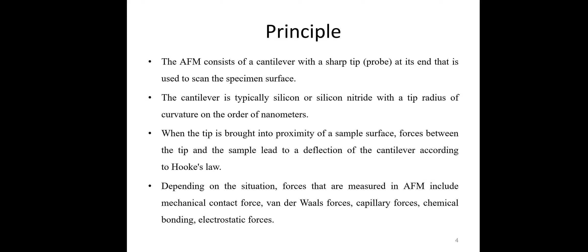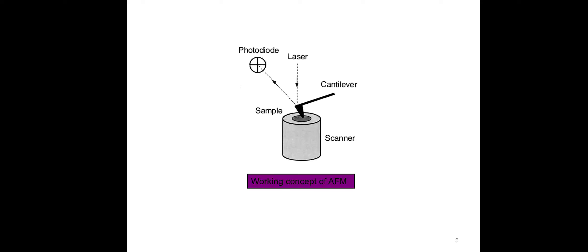Depending on the situation, the forces measured in AFM include mechanical contact force, Van der Waals force, capillary forces, chemical bonding, and electrostatic force. Here is the setup of atomic force microscopy — this is a piezoelectric scanner. We have a tip at the end of the cantilever. We move the laser to the end of the cantilever and generate different patterns.